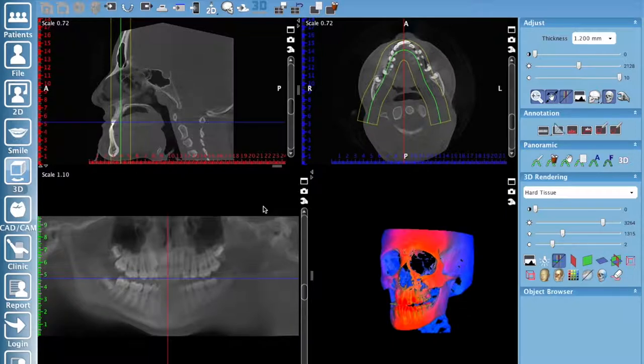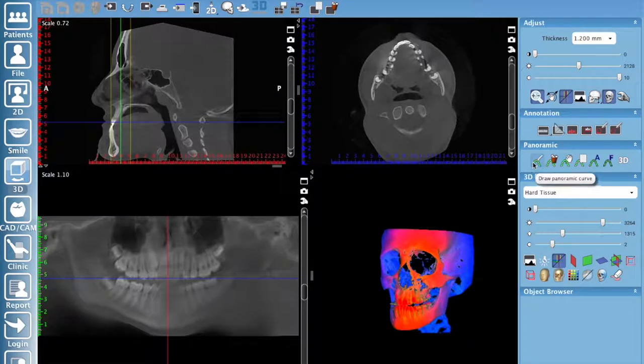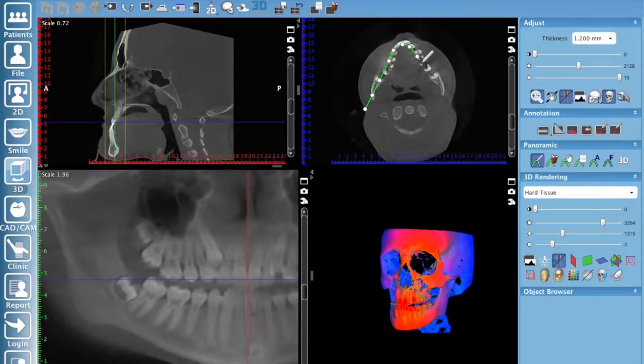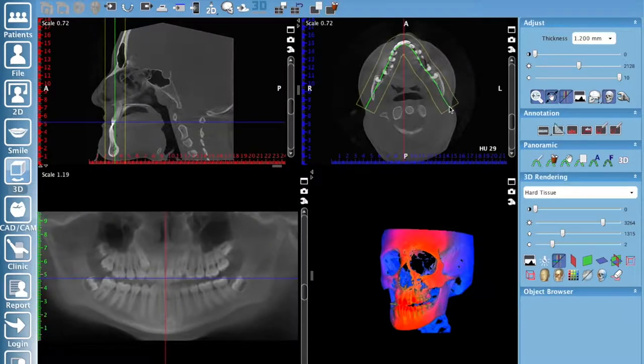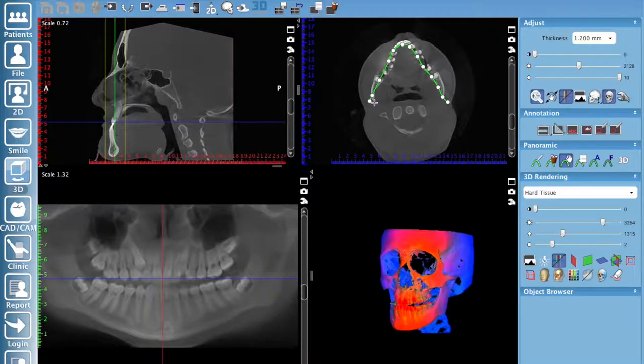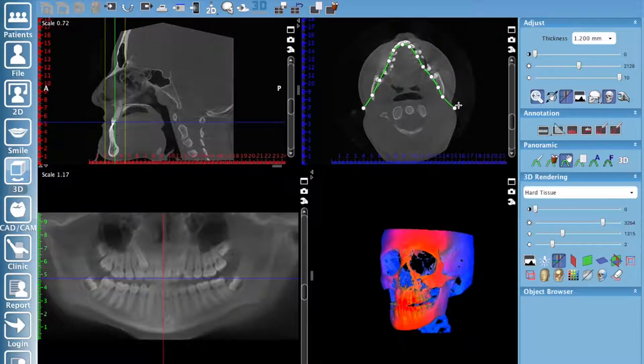You have a couple of options to make this look good. The software does its best to create the panoramic curve, but typically you'll want to adjust it. One option is to draw your own — select the pencil icon, left-click to set points, and double-click when finished. You can then use the edit points to move and adjust the curve, and drag the endpoints to extend it if the condyles are cut off.